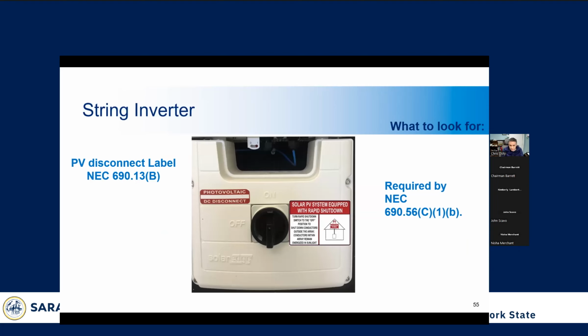All right. So lastly, we're going to take a look at the labeling requirements per NEC 690. This inverter has a disconnect handle built right into the inverter right here. It has to be labeled as the DC PV disconnect, and also that it has a rapid shutdown feature. String inverters have red rapid shutdown labels. And labeling is super important for future maintenance of the system, and so that people are aware of specific hazards within the enclosure, within the inverter, or whatever piece of equipment you're looking at, and also for first responders if they have to do anything with it.